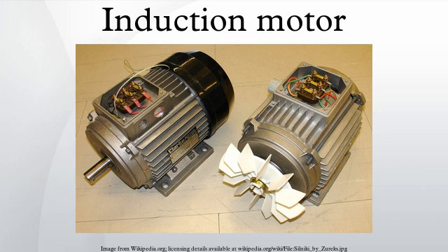Large slip ring motor drives, termed slip energy recovery systems, some still in use, recover energy from the rotor circuit, rectify it, and return it to the power system using a VFD. In many industrial variable speed applications, DC and WRIM drives are being displaced by VFD-fed cage induction motors. The most common efficient way to control asynchronous motor speed of many loads is with VFDs. Barriers to adoption of VFDs due to cost and reliability considerations have been reduced considerably over the past 3 decades, such that it is estimated that drive technology is adopted in as many as 30 to 40% of all newly installed motors.